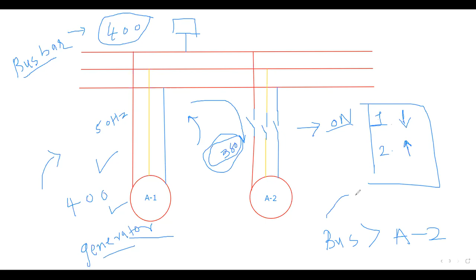That is why, before you connect alternator 2 with the bus bar, the first condition is that the bus voltage should not be less than this one. Otherwise, current will go into the alternator. Second is frequency. The frequency of this alternator should be equal to the frequency of the other alternator. This is very important. Third is the phase sequence. The R phase of alternator 2 has to be connected to the R phase, the Y phase to the Y phase, and the B phase to the B phase of the bus bar.